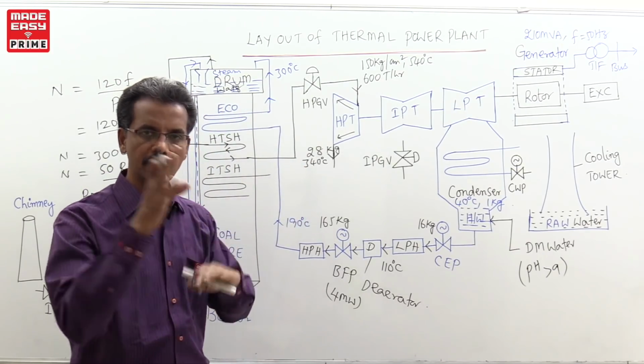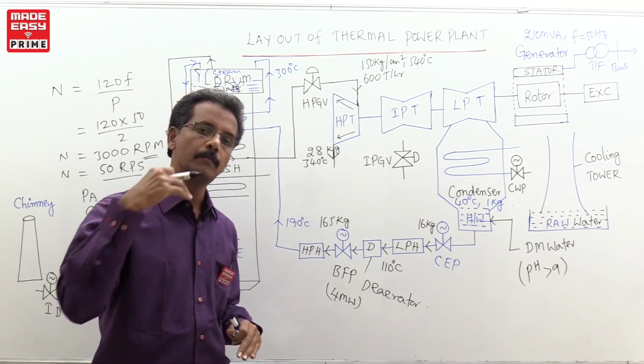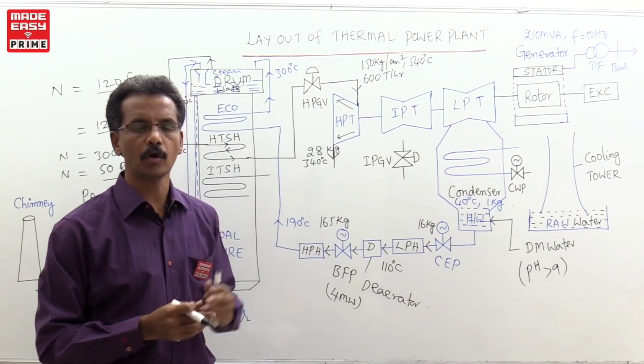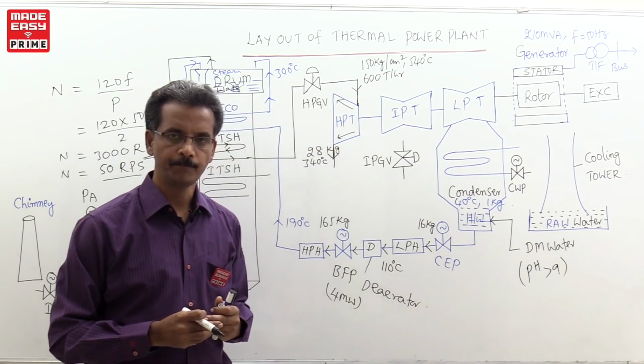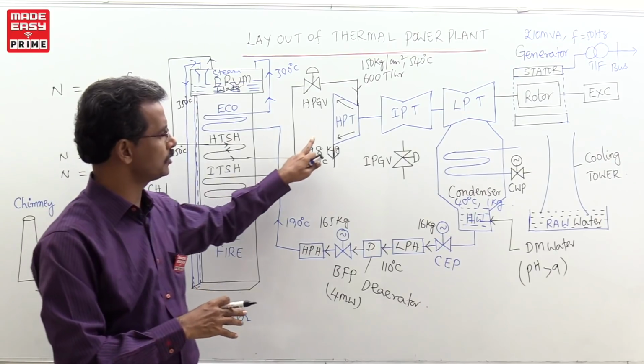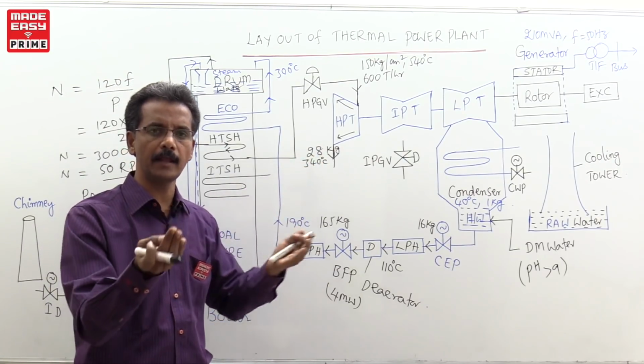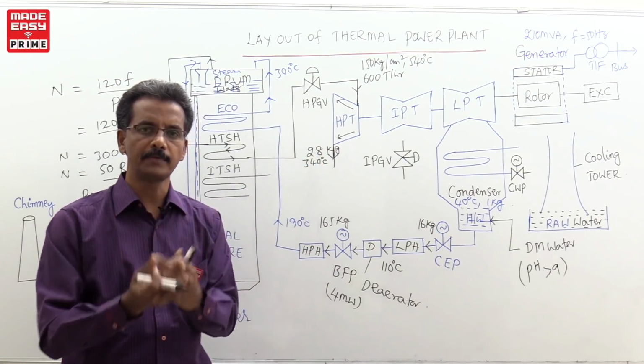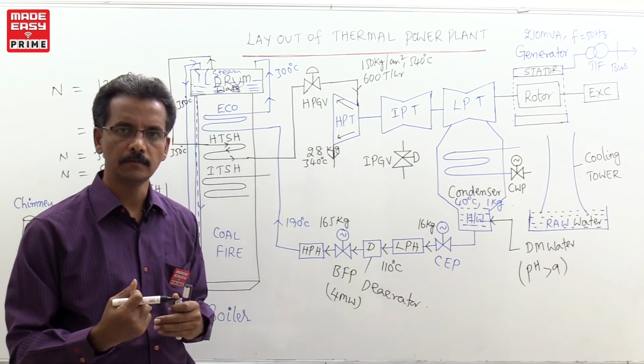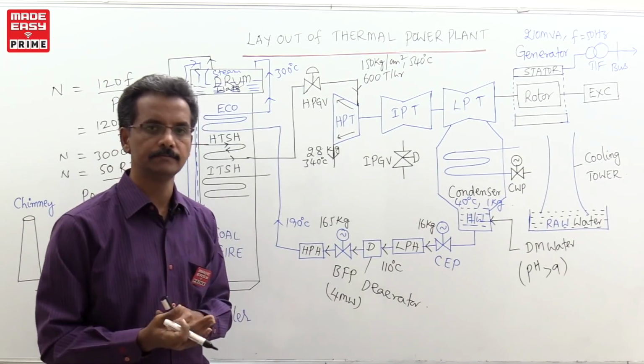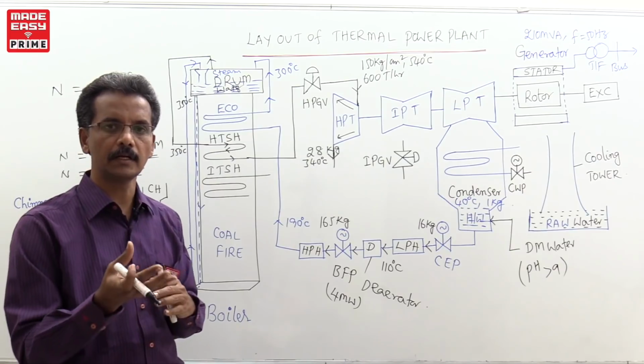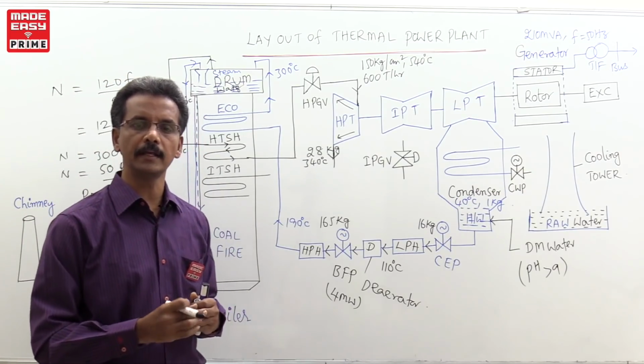This is the process they use in the case of low capacity turbines or low capacity generators. But here, a huge amount of pressure and temperature is there. Why would you convert this high pressure, high temperature steam into water? Instead of that, if you reheat once again, the efficiency of the thermal plant improves.